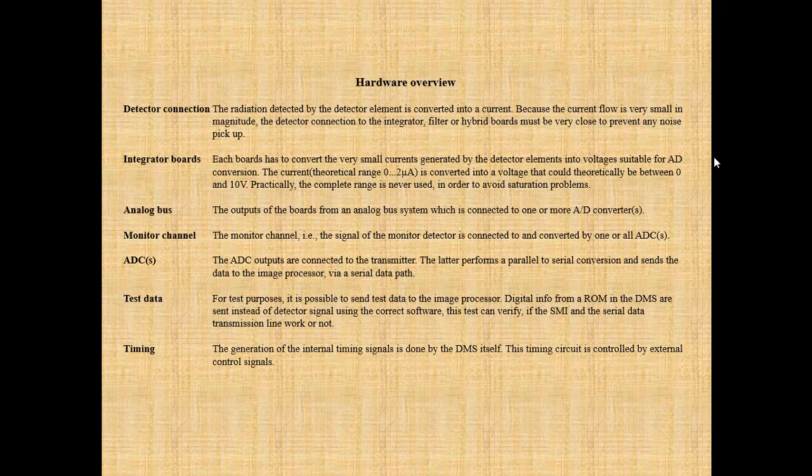Integrator boards: each board converts the very small currents generated by the detector elements into voltages suitable for AD conversion. The current, with a theoretical range of 0 to 2µA, is converted into a voltage theoretically between 0 and 10V. In practice, the complete range is never used in order to avoid saturation problems.